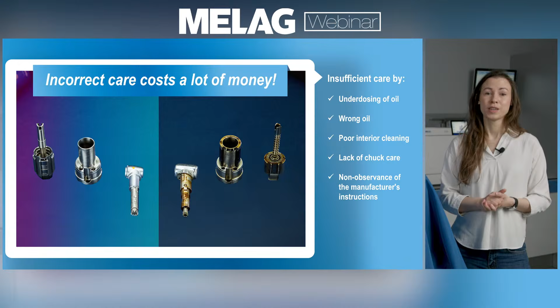Once we're talking about the reprocessing cycle at the end, according to international guidelines, recommendations, might be laws actually, we need to have some kind of risk classification. Whenever we bring an instrument to the sterilization room, we need to be sure what kind of purpose this instrument is actually given, so that we see what kind of steps we need to do inside the sterilization room. And in an international context, the main classification is actually non-surgical use or surgical use, non-invasive and invasive treatments. Let us start with the non-surgical treatments, such as conservative instruments and treatments. What steps do you need to do to follow the hygienic cycle?